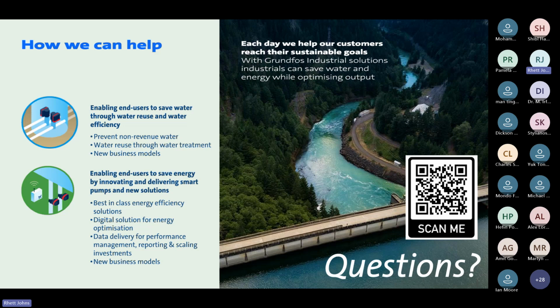You don't necessarily have to always split the flow over multiple pumps, but you can rather just ensure that you have maybe 2 pumps that are operating at the correct size. So reduce your motor size, maybe have a smaller pump hydraulic so that it's running more efficiently, and that's going to give you good savings at that point.